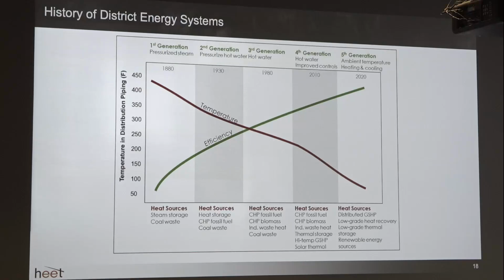So before I pass it to my colleague Nick, I thought I'd throw in a little segue slide here. I believe one person had a similar slide yesterday where it looks at the temperature and the distribution piping of district systems. And over time, we used to use really high temperature, right? I mean, we still do today, pressurized steam, but that leads to low efficiency. And so over time, we've been able to reduce our temperature in our distribution piping, which has led to an increase in efficiency. So now we're dealing with ambient temperatures, which has increased our efficiency in these district energy systems quite dramatically.